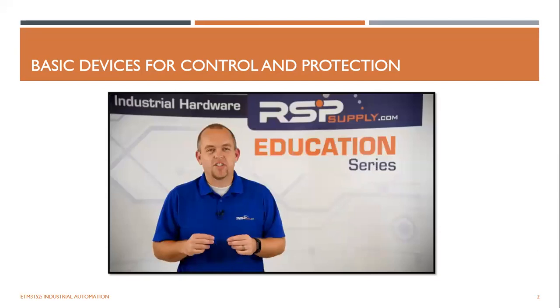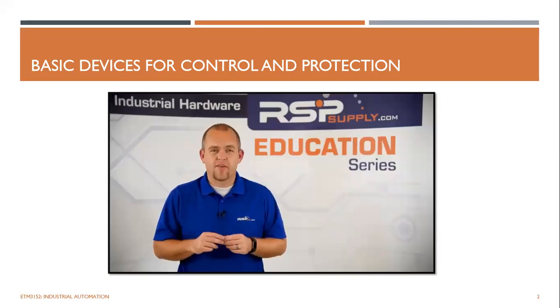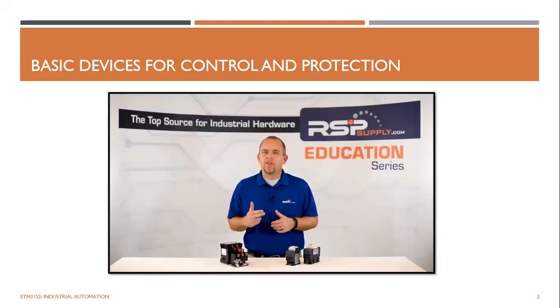Another type of protection that is used in place of motor circuit protectors is some type of fused disconnect. However, it is important that we use fuses that are designed for this type of application. So let's talk about a few things that we want to consider when we're purchasing a motor starter. First, we want to determine whether we need a NEMA starter or an IEC starter.